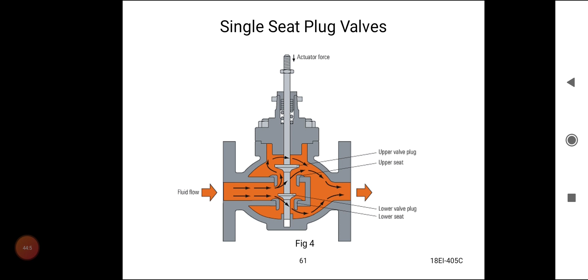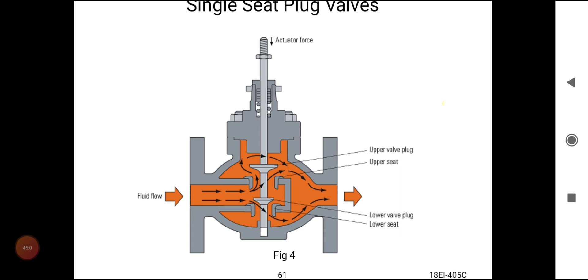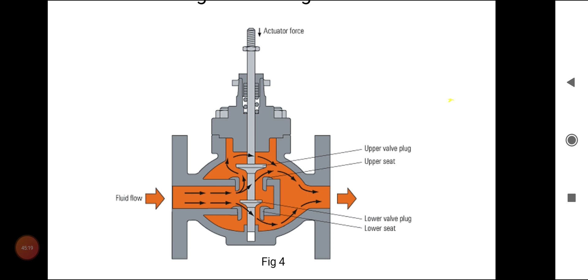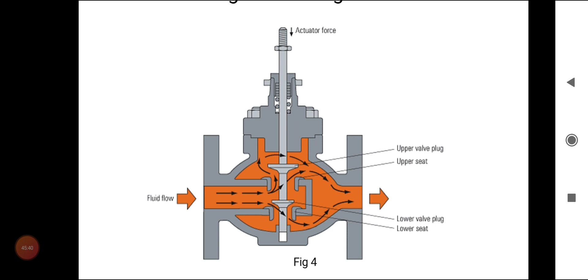The differential head pressure acting on the plugs, seats and stem can be reduced. There are the upper valve plug and upper seat, and the lower valve plug and lower seat. The actuator force causes the stem to move inside the valve body. The two plugs are attached and pinned to it, so the area opening of the seats can be varied by these plug movements, which is an advantage compared to the single seat plug valve.